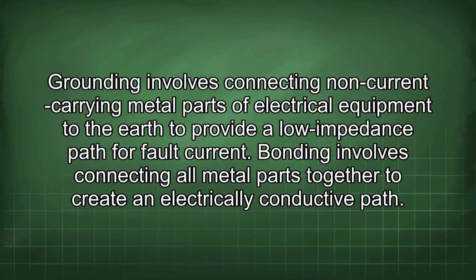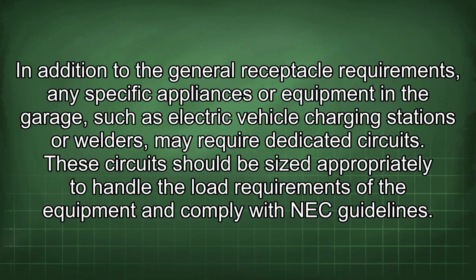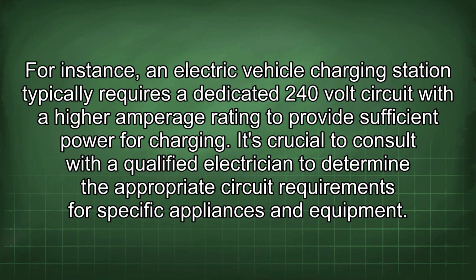Grounding involves connecting non-current carrying metal parts of electrical equipment to the earth to provide a low impedance path for fault current. Bonding involves connecting all metal parts together to create an electrically conductive path. In addition to the general receptacle requirements, any specific appliances or equipment in the garage, such as electric vehicle charging stations or welders, may require dedicated circuits. These circuits should be sized appropriately to handle the load requirements of the equipment and comply with NEC guidelines. For instance, an electric vehicle charging station typically requires a dedicated 240-volt circuit with a higher amperage rating to provide sufficient power for charging. It's crucial to consult with a qualified electrician to determine the appropriate circuit requirements for specific appliances and equipment.